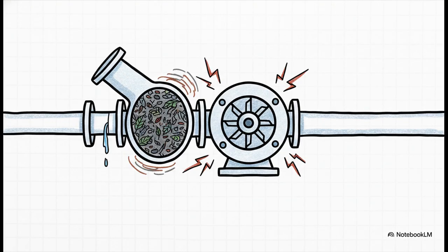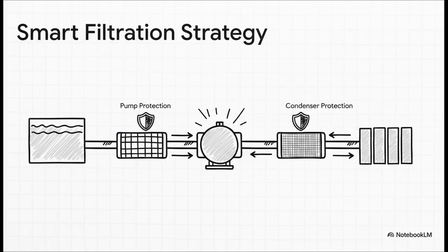And now for filtration. You know, strainers are absolutely essential, but where you put them is critical. And I mean that. Putting a strainer in the wrong place can be even more dangerous than not having one at all. A clogged strainer can ruin even the most perfectly designed system. So here's the smart strategy. First, you protect the pump. Use a coarse, large mesh strainer right at the tower pan. It'll stop the big stuff, leaves, debris, whatever, and it's easy to clean. Then, you protect the really sensitive condenser tubes by placing your fine mesh strainers on the discharge side of the pump. That's the high-pressure side, where they can't possibly starve the pump of water.